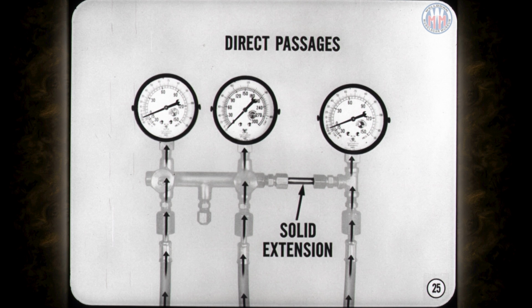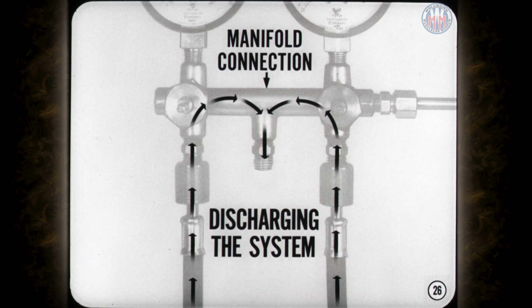What's the story on the manifold valves? Do they control the gauges? Nope. The gauges have direct passages through the manifold, so they can indicate pressure with the valves open or closed. The inlet pressure gauge at the right side connects directly to its hose. The solid extension from the manifold is only an attaching mount for the gauge. Actually, the valves only control the flow to and from the center manifold connection, which we use for charging or discharging the system. Some gauge sets also have an adjustable needle valve to slow down the discharge gauge pointer movement.